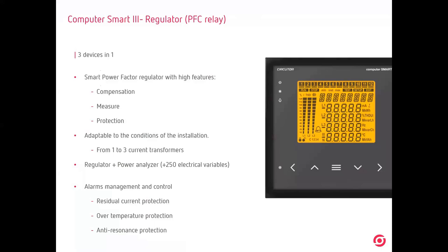So if we want to reach power factor one, we should measure with three current transformers, because we are measuring the total RMS value of the three-phase line. If not, we will be overcompensating or not reaching the value that we need. If we are overcompensating, we can have penalties by capacity. So if you don't have penalties, you can use one. If you have imbalance or you have penalties, please use three current transformers, because you will read exactly the reactive energy that is flowing through your cables, and you will connect the steps that you really need to compensate to the cos phi that you set.